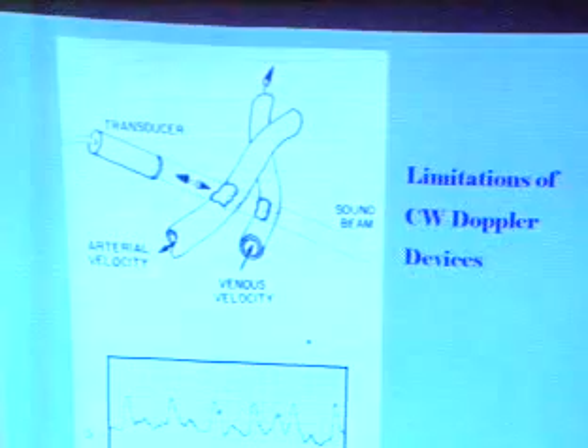Now, while we were moving forward in the vascular area, there was increasing interest in applying Doppler techniques on the heart. And if you attempted to use a continuous wave Doppler, it had no range resolution. It picked up everything in the field of view along the beam. And so we see here, for example, a vein and an artery combined together. And CW worked good in a peripheral vascular application where you didn't have other moving structures. But you could put it on the heart, and you could hear valves clicking, you could hear wall motion and so on, but you couldn't separate them. In spectrum analysis, we just got a huge mess of things. You couldn't do that. So that led to conceiving of the pulse Doppler.